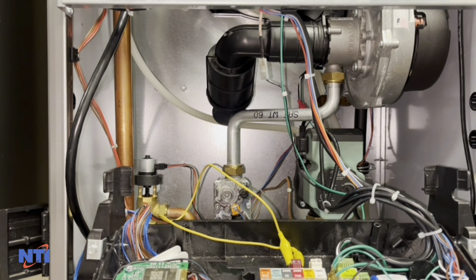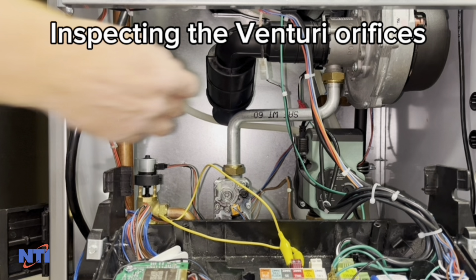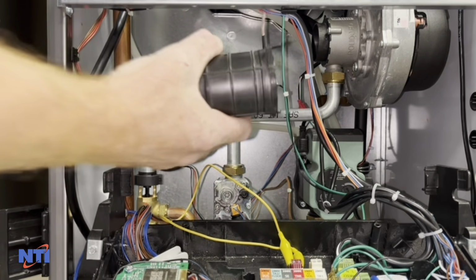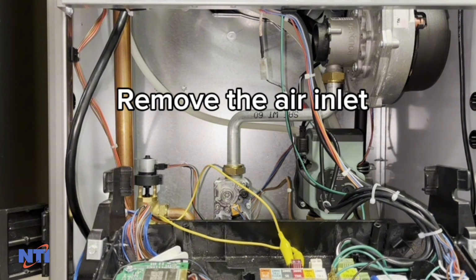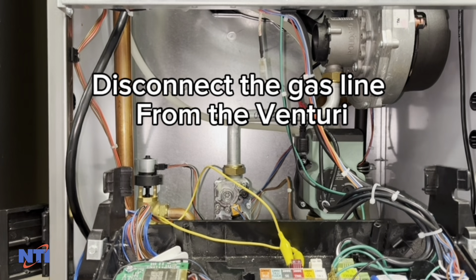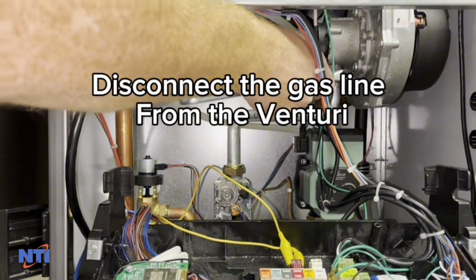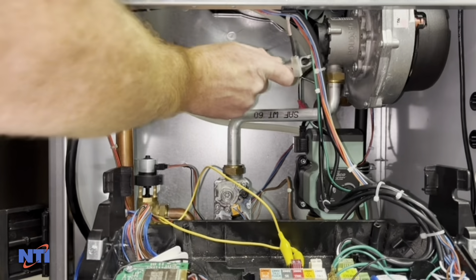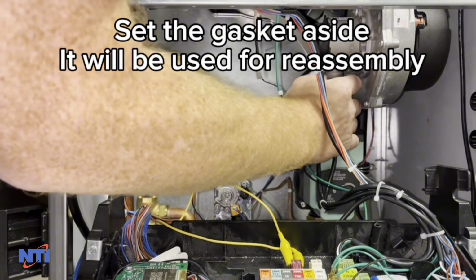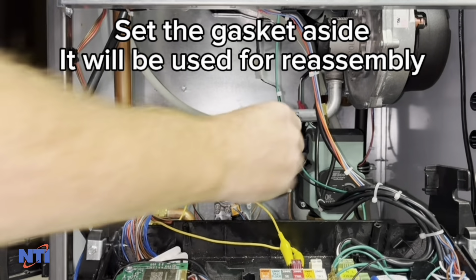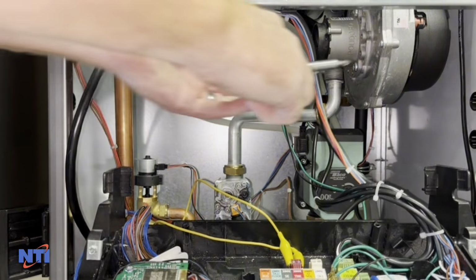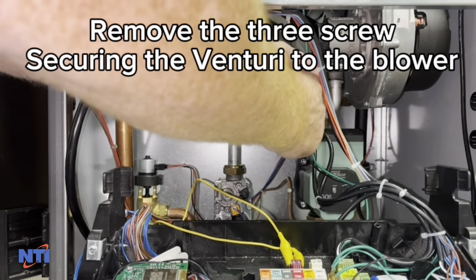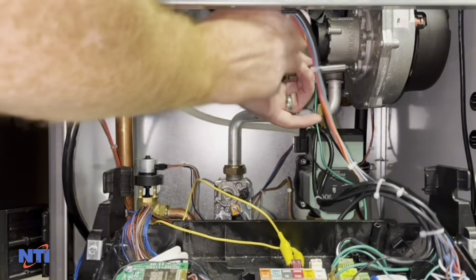If the boiler is still not lighting, start by inspecting the Venturi orifices. The gas line must be removed from the Venturi. Use care not to lose the gasket as it will be required for reassembly. There are 3 screws securing the Venturi to the blower assembly. Once these are removed, the Venturi can be taken off the boiler.